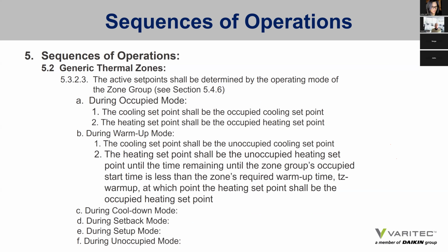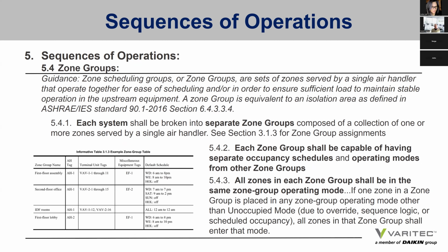There's going to be an occupied mode, warm-up mode, cool-down mode, setback mode, setup mode, and the guideline defines which of those modes need to be enabled when, depending on the time of day and occupancy. It goes on to define what a zone group is more thoroughly. Zone scheduling groups or zone groups are sets of zones served by a single air handler that operate together for ease of scheduling or in order to ensure sufficient load to maintain stable operation in the upstream equipment. It goes on to say that each system shall be broken into separate zone groups appropriately composed of a collection of one or more zones served by a single air handler.